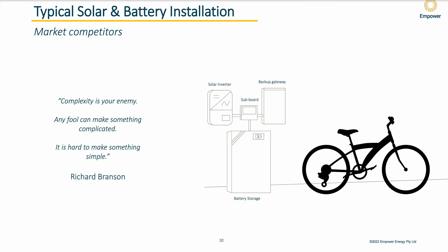In terms of the gateway or the changeover switch, what we've said before is you could put an external automatic transfer switch into a switchboard, but you need to control that. So you're going to run just an AC cable to it to control it, or a comms cable? Yeah, so the simplest way is to just put the grid volt straight onto the coil. So the grid volt itself controls it, yes.